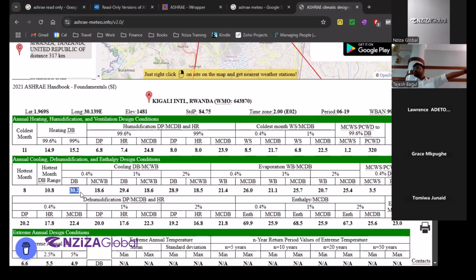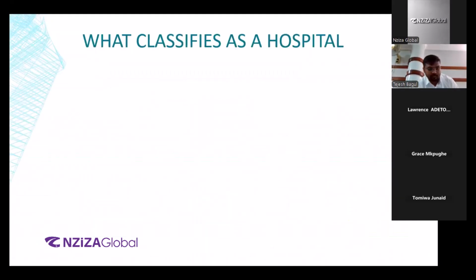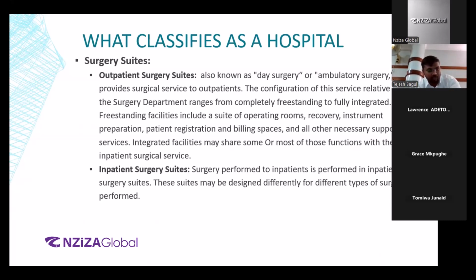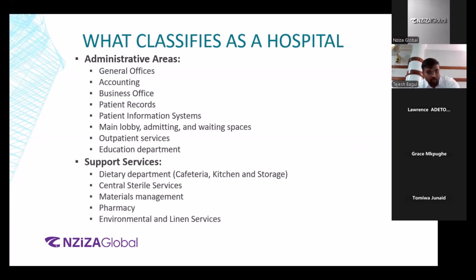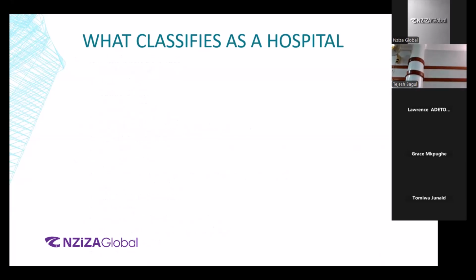Is that making sense? So now my air handling unit, my HVAC system that I'll be designing, indirectly my cooling coil, will be designed for 30.2 degrees centigrade outside. Inside, let's say what did we have previously? 21, okay, yeah, 21 we are talking about, right? So 30 minus 21, the 9 degree, so that 9 degree is the delta T that I'm calculating.